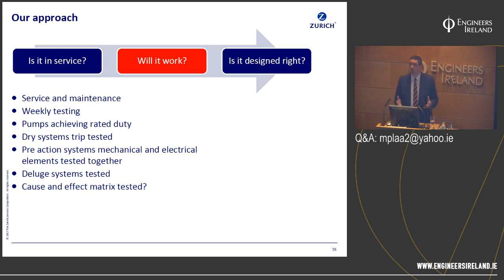And what about pre-action systems where we've got detection and we've got mechanical deluge or discharge of water? Can you be confident that when that detector goes off, it discharges water into that space? In most cases, the detection contractor will have done their bit, the water mist contractor will have done their bit, but they wouldn't have joined together to prove both elements talk to each other. And it's one of the big failings we find in the field. And again, the cause and effects matrix. If you have one that says the conveyors stop, the fire doors come down, the lifts stop, have you proven it?